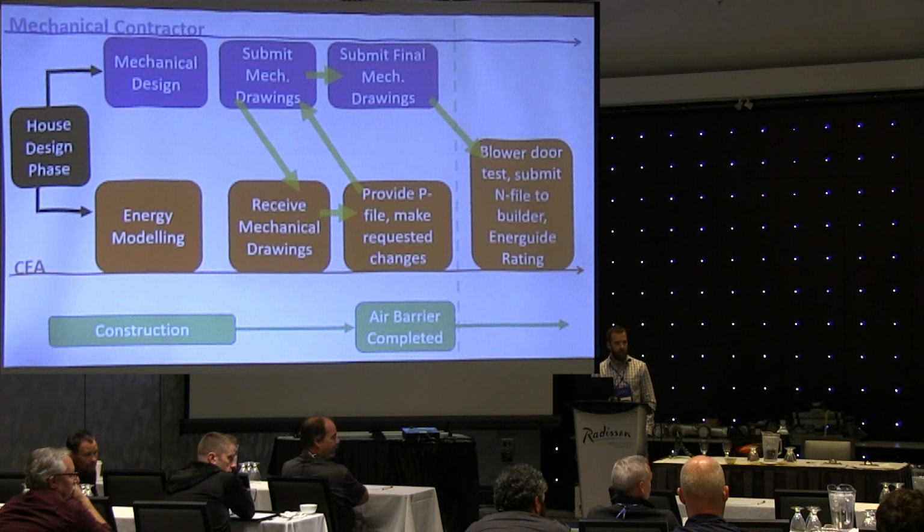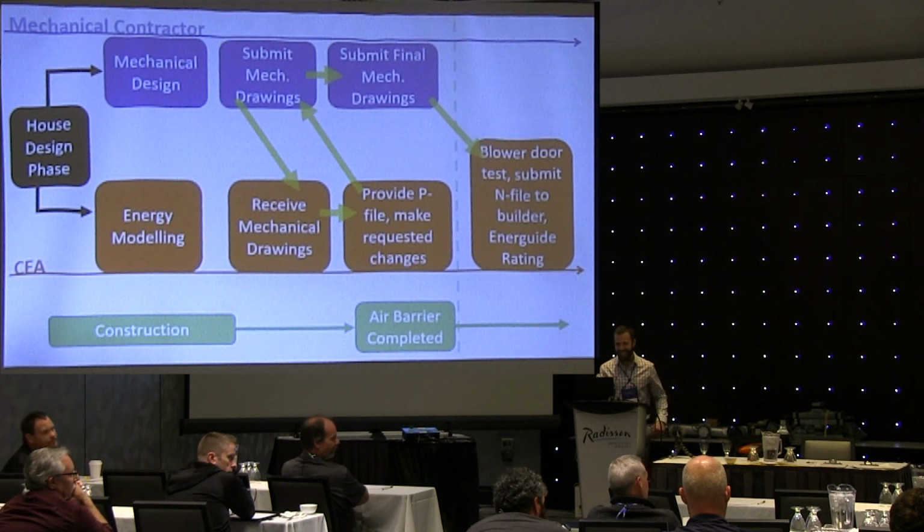What you may not know is as soon as you start building a house with a blower door standard, the hot air will not rise because there's no escape for it, and you'll find that your whole top floor becomes underheated, which was discovered in the R2000 program 25 years ago, that we were short in the delivery to the second floor because we've been getting a free ride on shit leaky building practice for 30 years. We continued the same practice and we got burned with the top floor not heating.